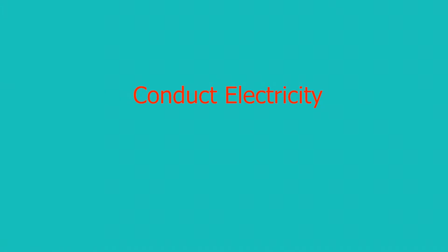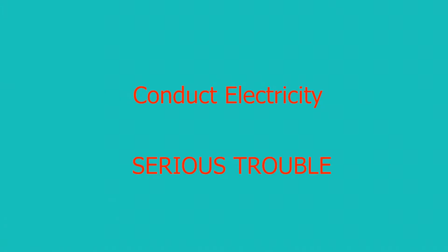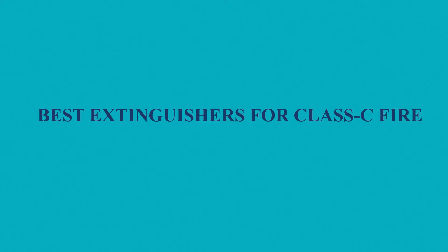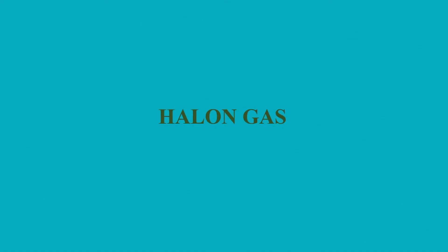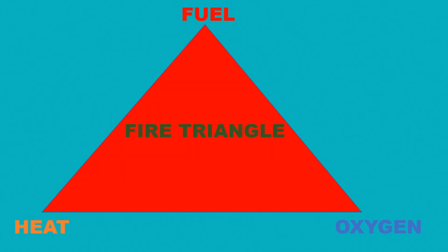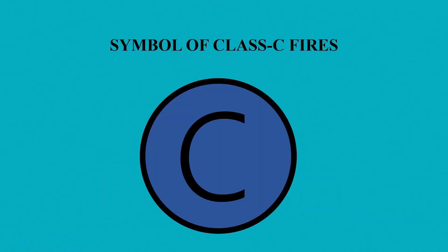Never use water, foam or any solution containing water on electrical fires, as these materials can conduct electricity and can result in serious trouble. The best extinguishers in case of electrical fires are dry chemical powder, CO2 or halon gas. Class C fires are extinguished by taking away the heat element of the fire triangle. These fire extinguishers are denoted by a circle symbol with blue color and capital letter C.